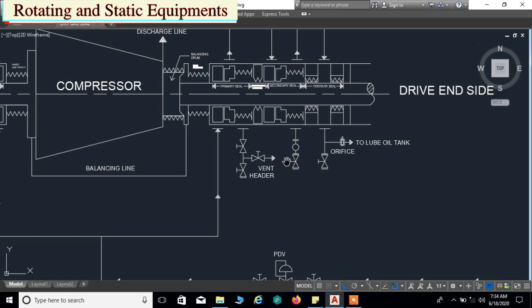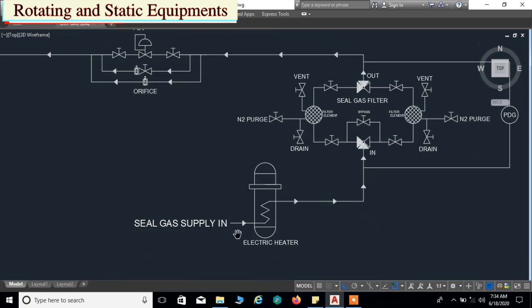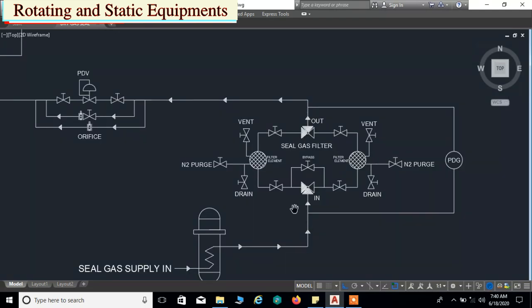Now we will see the seal gas supply. This is the seal gas supply inlet. To ensure that the seals operate with condensate-free clean gas, filtered gas is injected at a pressure slightly higher than the suction pressure. For example, if the compressor operating suction pressure is 1 bar, the seal gas pressure will be 1.5 to 3 bar. The seal gas is first preheated by an electric heater to a certain temperature, then passes through a filter for removal of foreign material, dust, and minor carbon particles.